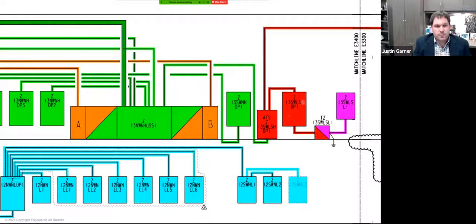In this particular case, these distribution panels were feeding some large air handling units. I think we had 80,000 CFM air handling units in this facility, 100% outside air. And we had very, very large laboratory exhaust systems. So these systems were feeding those. Some of them were on emergency power, some of them weren't. I'm not going to get into that too much.